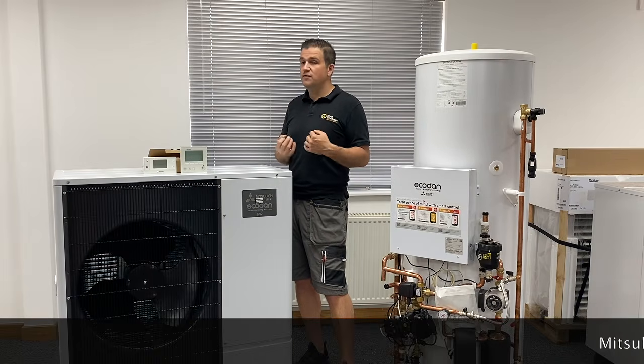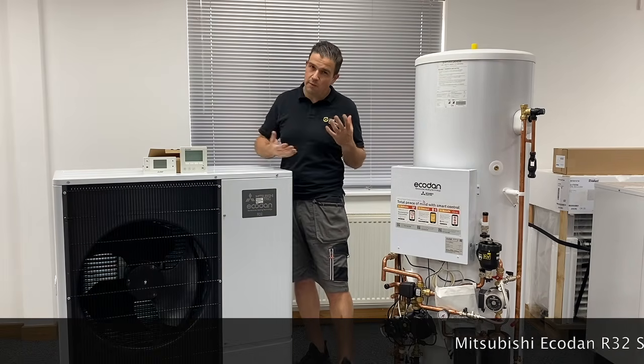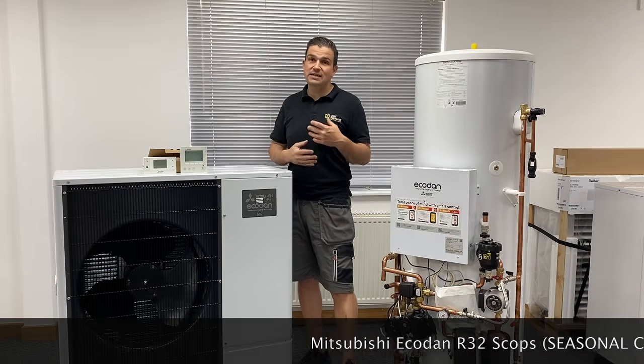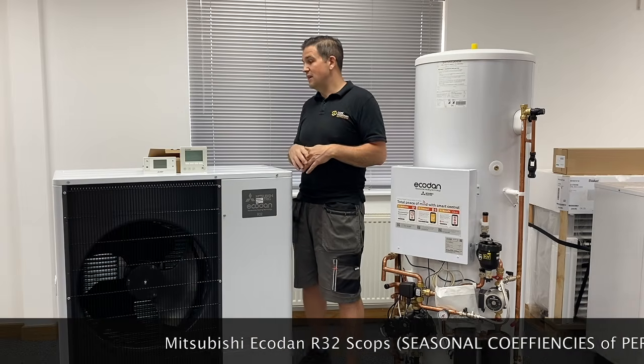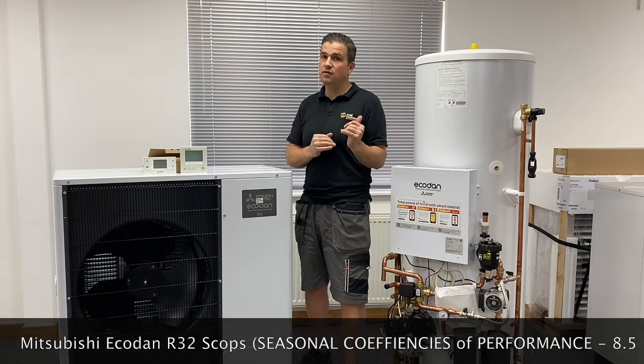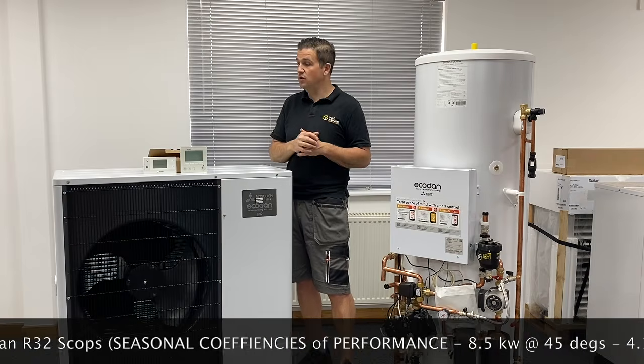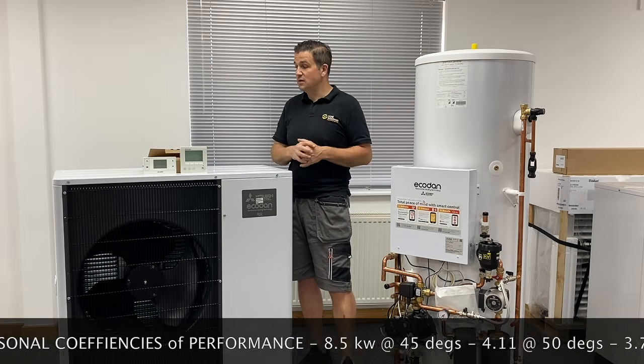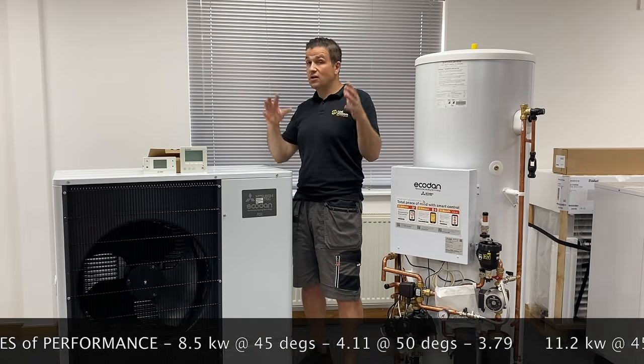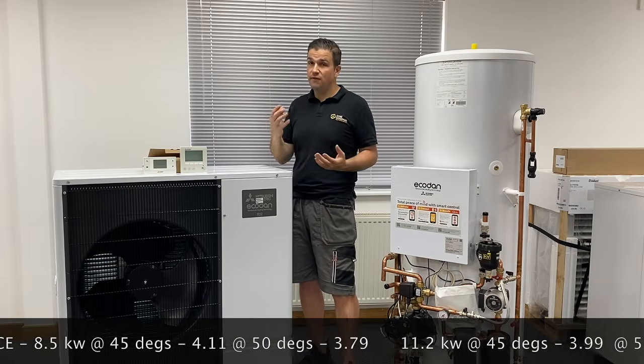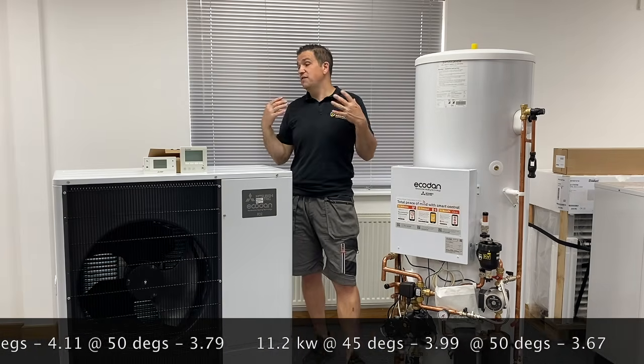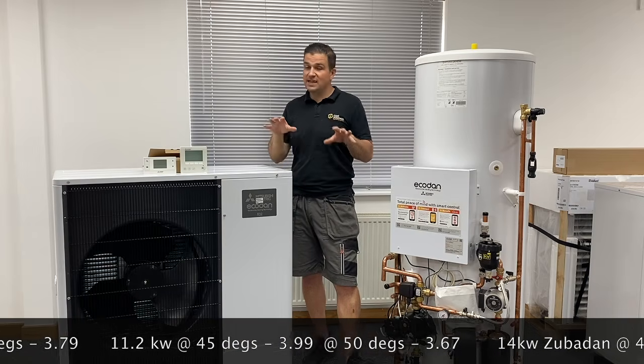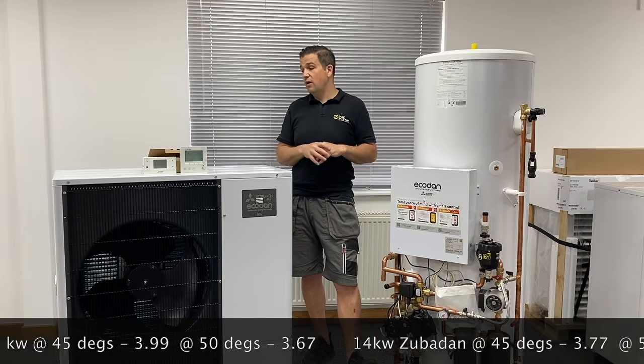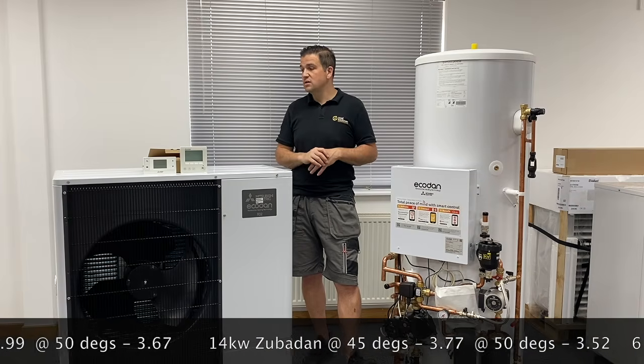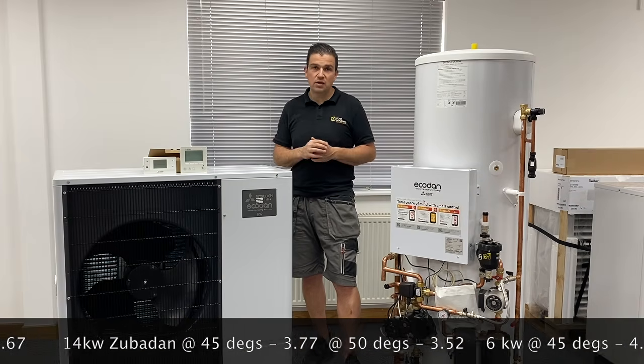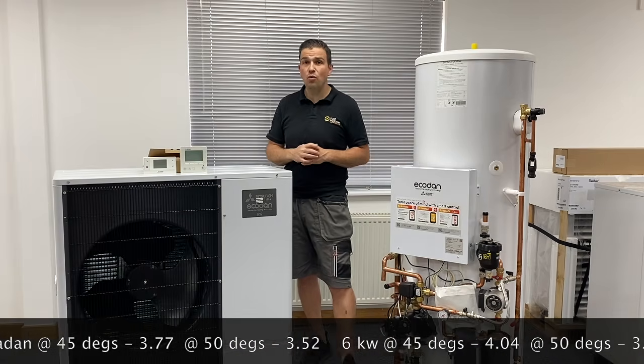So the 8.5, for instance, at 45 degrees, it will give you a SCOP of around about 4.1. At 50 degrees, the SCOP is 3.8. The 11.2 is very similar, but it's just under the 4 mark on the 45 degree temperatures. It's 3.9. And then when we get to 50 degrees, 3.6. On the much larger model, so the 14 kilowatt, you'll be looking at 45 degree temperatures about 3.7, 50 degrees about 3.5. And then when we get to the smaller units, so the 5s and the 6, we've fitted those in a few of the newer builds. So they're a smaller heat pump, more than capable of delivering a good heating and hot water demand.